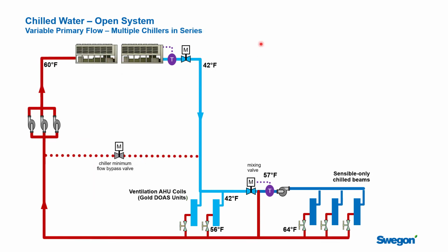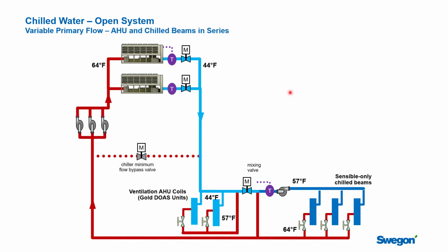Alternatively, you might want to consider looking at putting them in series. This is a nice arrangement. If you have a large delta T across your plant, it can actually improve the efficiency of the chillers, and something you might want to consider. And it's a nice segue into something that we talk a lot about with chilled beam plant design, which is if you look at the water we need to go to the air handling units where we have to do the dehumidification, the return water from the air handling units is pretty close to the supply water temperature that you would need out at the chilled beams.